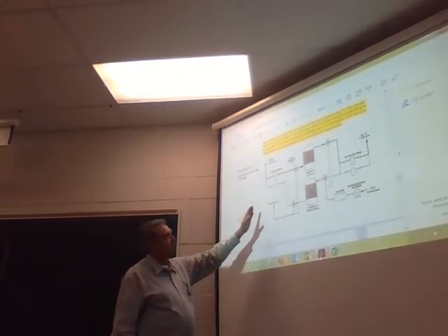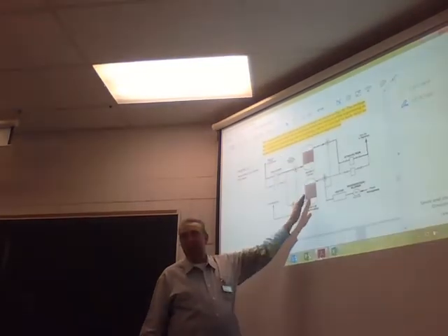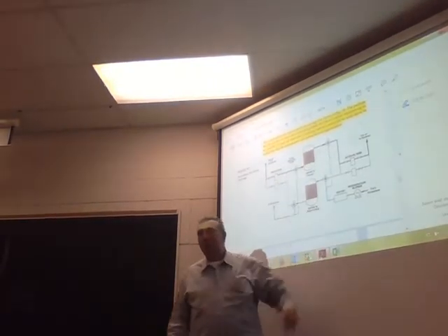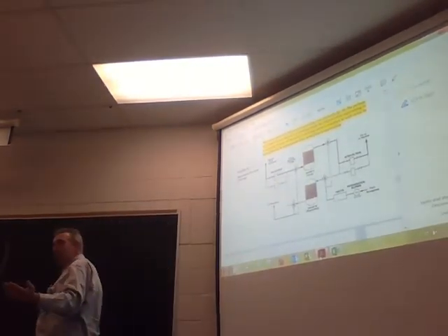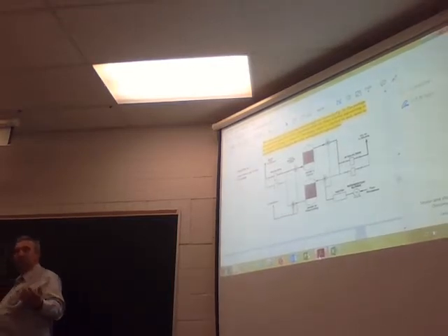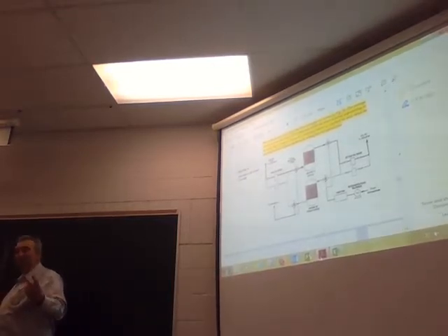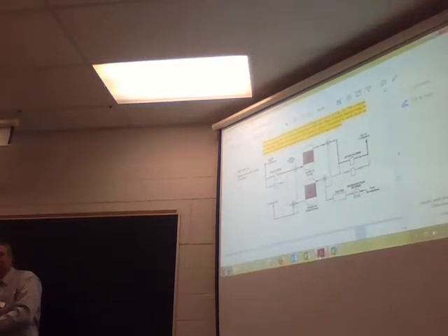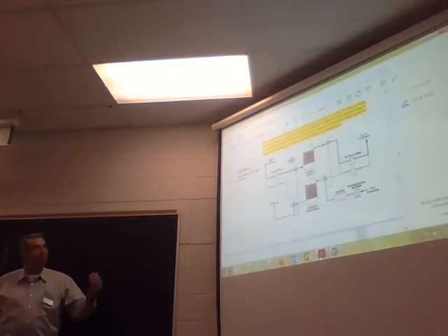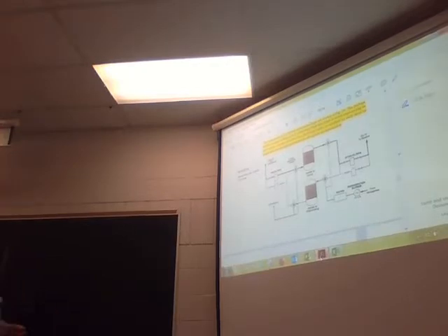We've got a three-way valve because we've got two dryers, one that we can be regenerating, one that's actually doing the drying. When you were on your co-op and you had a sodium zeolite softener, did you have two of them? Yeah, one so you could take it out of service and regenerate while the other one goes on. Same idea.